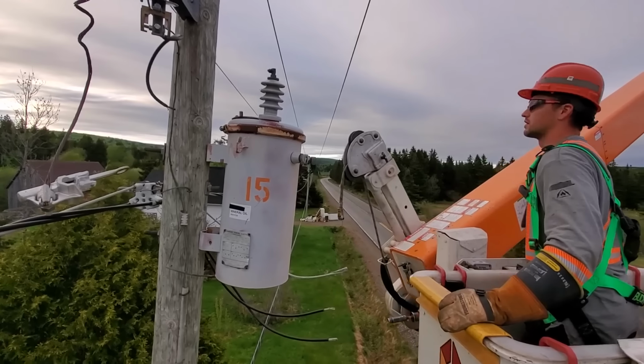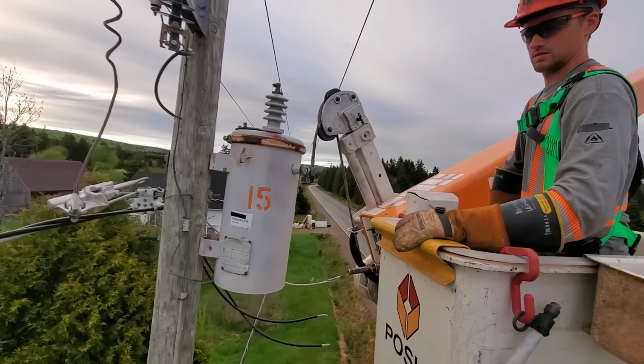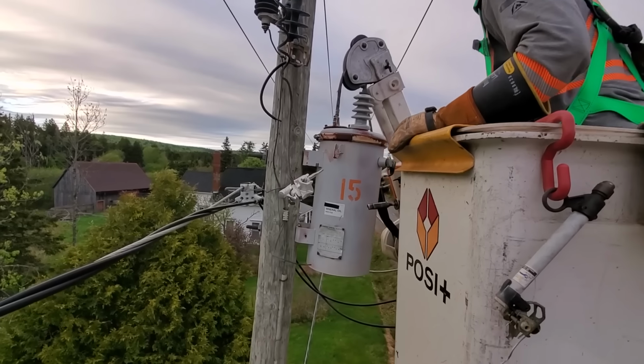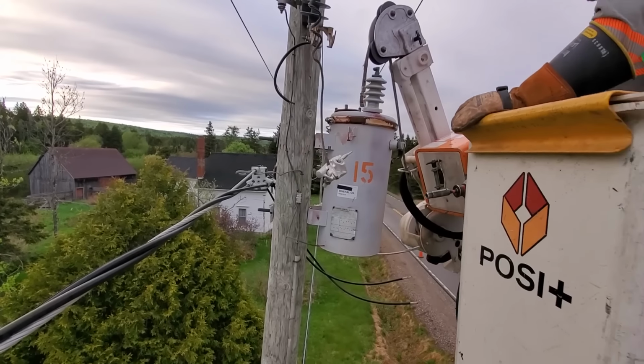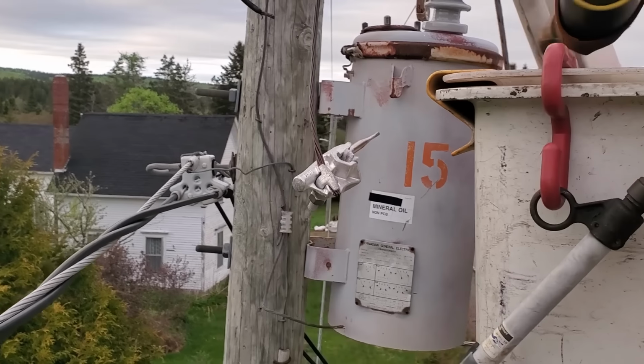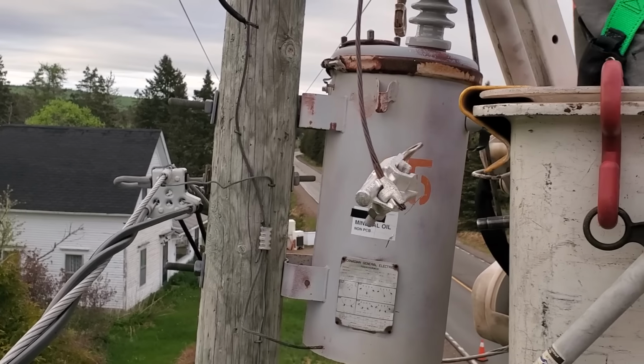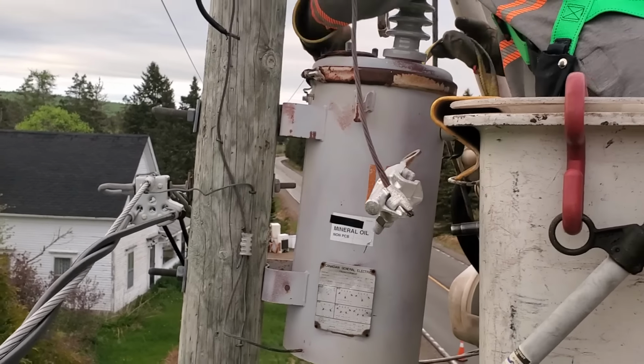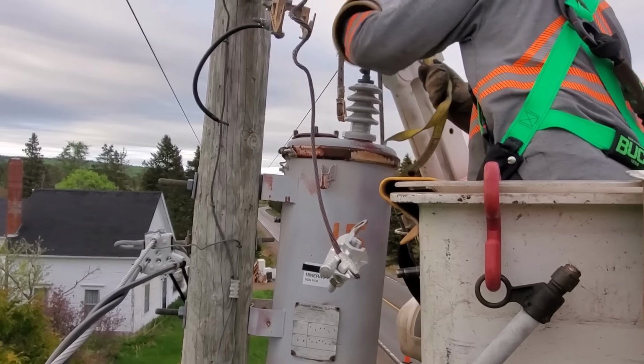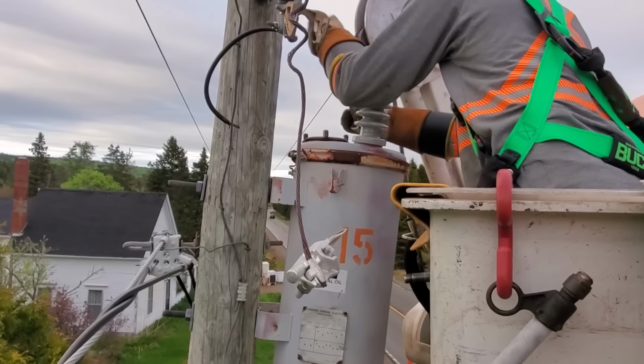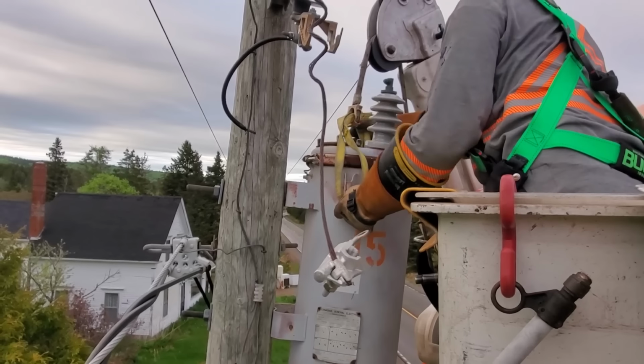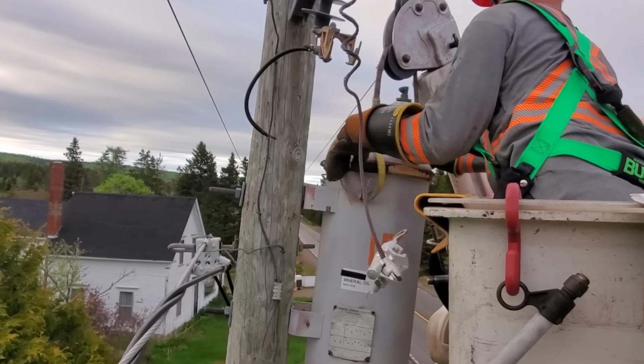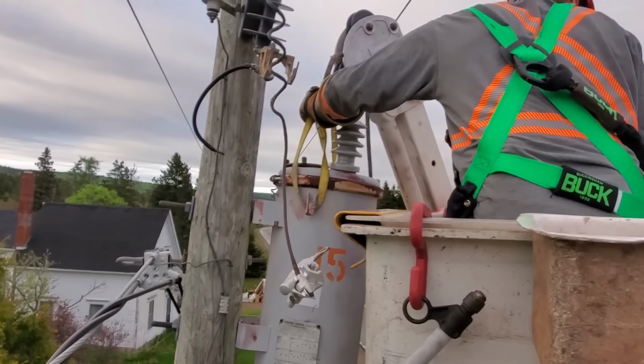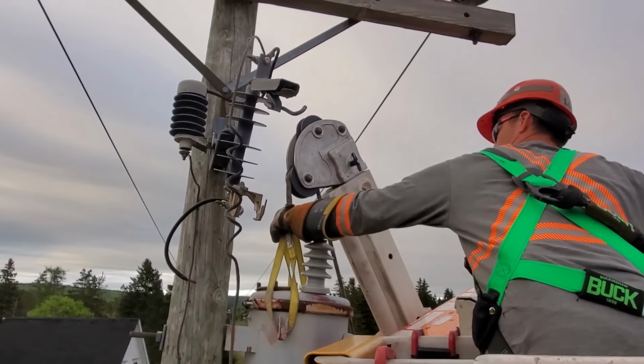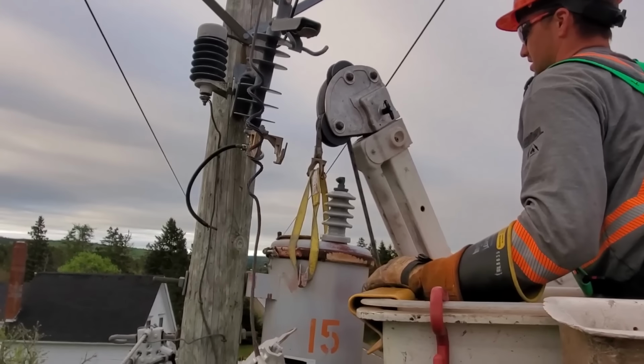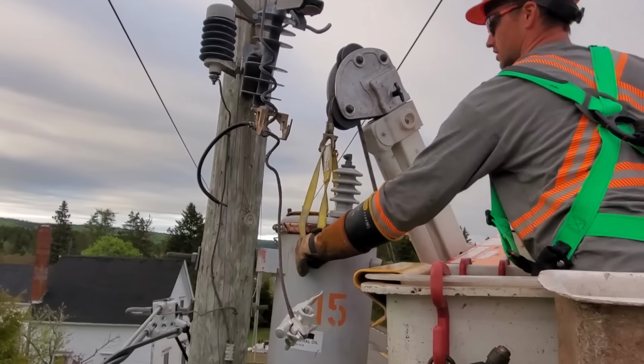The jibs in these newer trucks compared to our older ones make this job much easier. They're quite versatile. So he's got both the bottom and top bolts loosened off on that transformer. Those are 3/4 inch machine bolts. You want to make sure that you keep that strap as low as possible. Here, he's got quite a bit of space, so as he extends that jib up, it's going to lift up an extra couple inches, but he's still got enough clearance from the primary. If we felt we were getting too close, we could put some hard cover up on that primary.